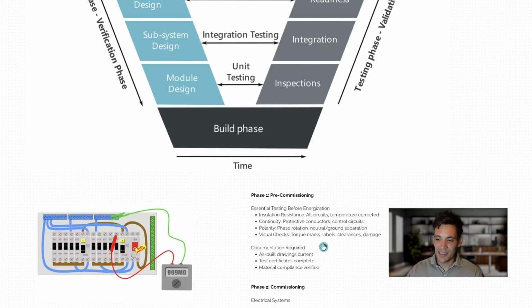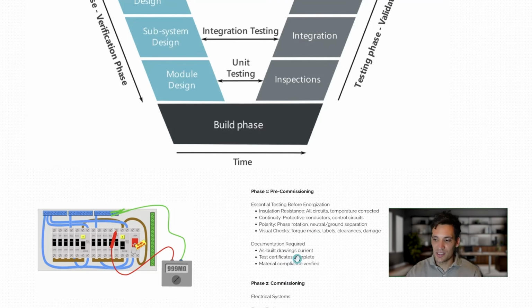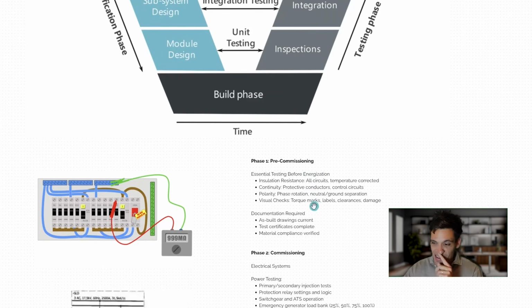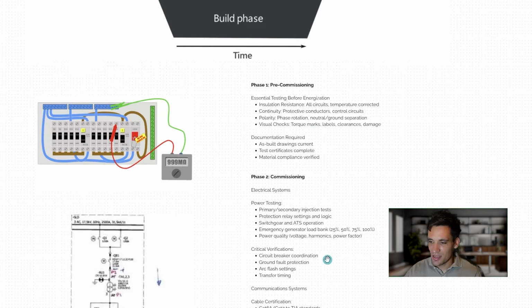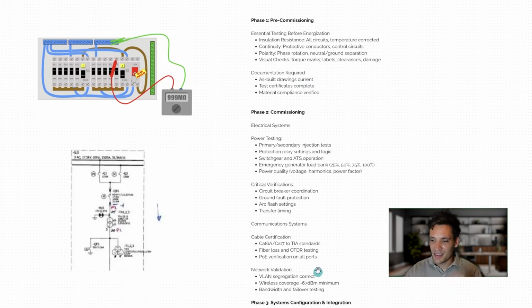We do continuity testing to test the cables have been run from point A to point B correctly, as per the drawings. We do polarity checks to check the red, green, and blue has been installed correctly. And we do visual checks that there's torque marks, labeling's installed, there's clearance, there's no damage. And we document this with the construction as-built drawings and test certificates. Once the construction quality assurance and pre-commissioning is done, we're 100% confident that what we've built matches the IFC design, which is when we can go into the commissioning test.